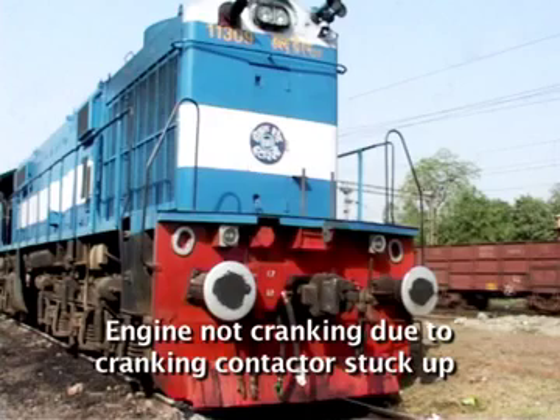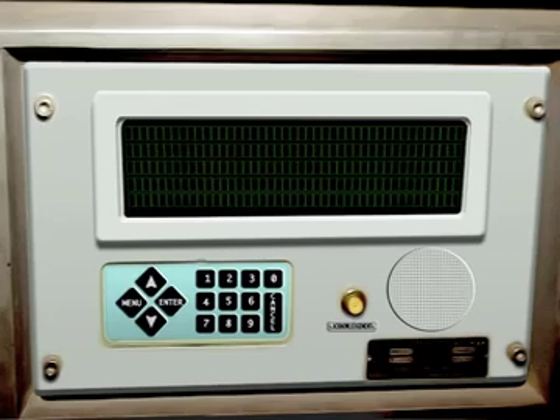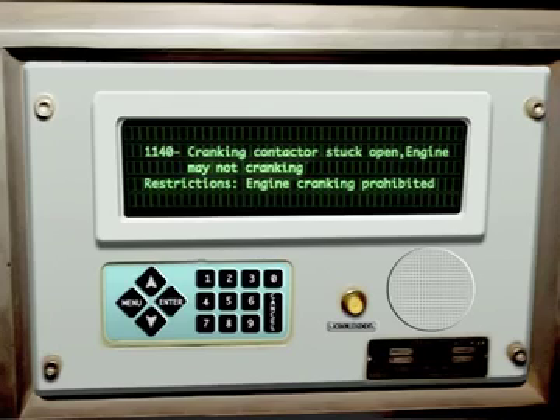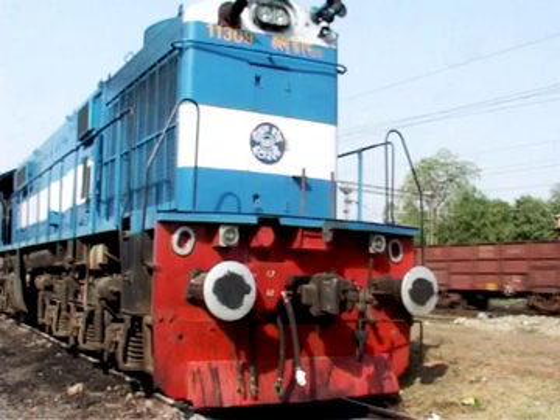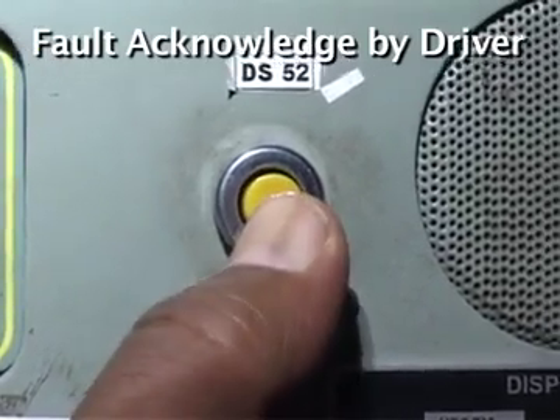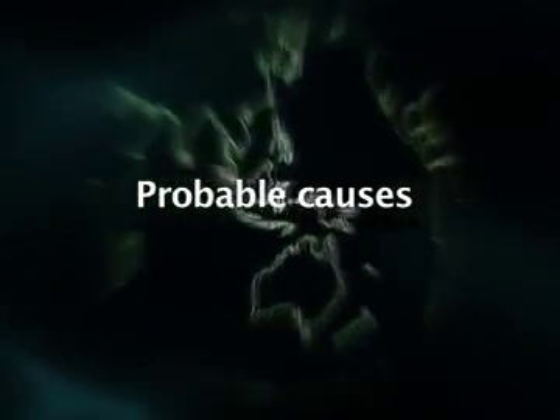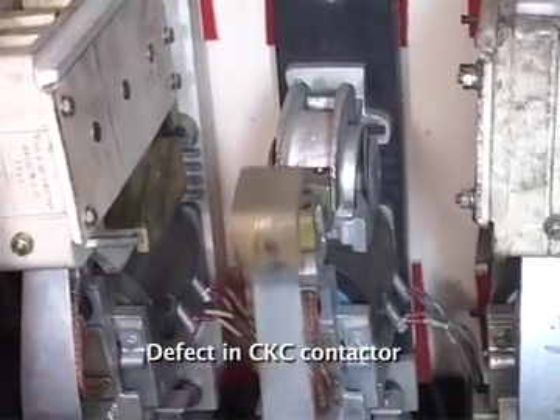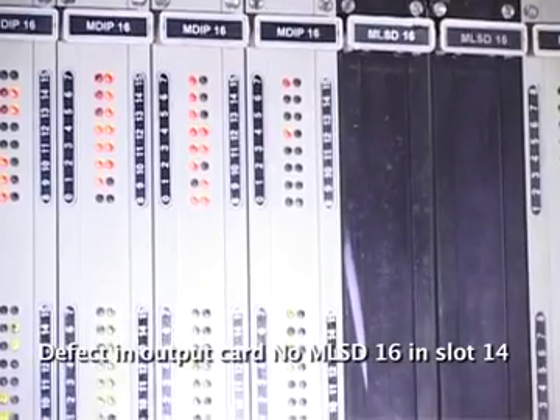Fault message coming. Cranking contactor stuck open. Engine may not crank. Message code 1140. Restriction: engine cranking prohibited. Alarm bell ringing up to 5 seconds. Driver acknowledging fault.